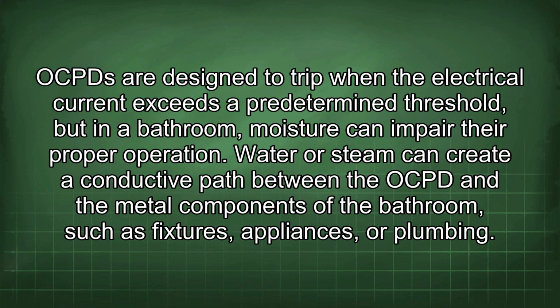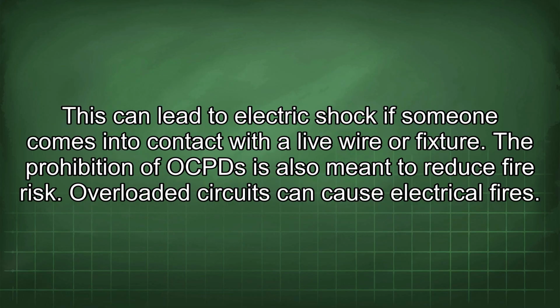OCPDs are designed to trip when the electrical current exceeds a predetermined threshold, but in a bathroom, moisture can impair their proper operation. Water or steam can create a conductive path between the OCPD and the metal components of the bathroom, such as fixtures, appliances, or plumbing. This can lead to electric shock if someone comes into contact with a live wire or fixture.